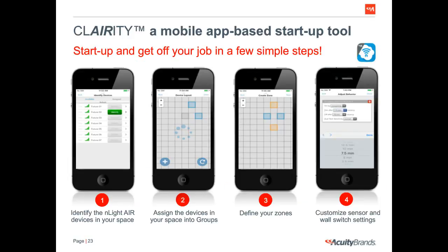Clairity, the mobile application -- a major feature behind Clairity is that every time a job is started up or installed, all that information, the settings, the devices, the spaces, is all saved into the cloud. So we have a record of what's been set up, what's been commissioned properly, and what the settings are for the occupancy and daylight sensors. We can reference those to ensure we're up to code, and go back if there's any need to troubleshoot -- we can see what the initial settings were and what the most recent changes have done to the system.